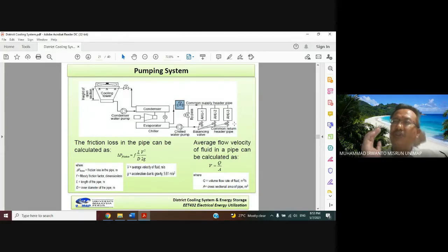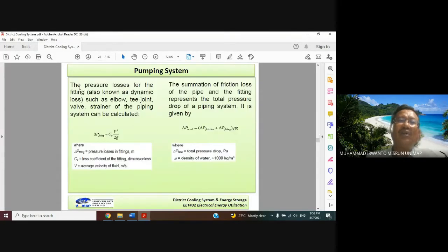So we also consider the friction loss from the elbow, T-junction, strainer, and valve. These are called the fitting or pressure losses, also known as dynamic loss, from elbow, T-junction, valve, and strainer of the piping system. It is calculated using this formula: delta P fitting equals Cf multiply V power 2 over 2G.